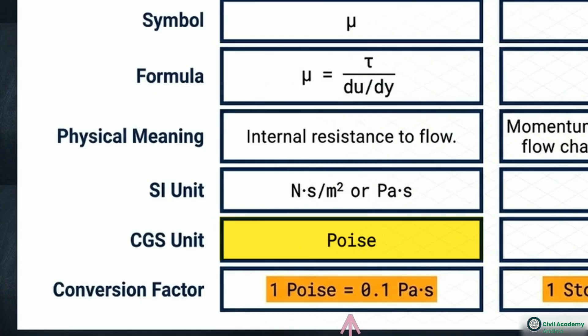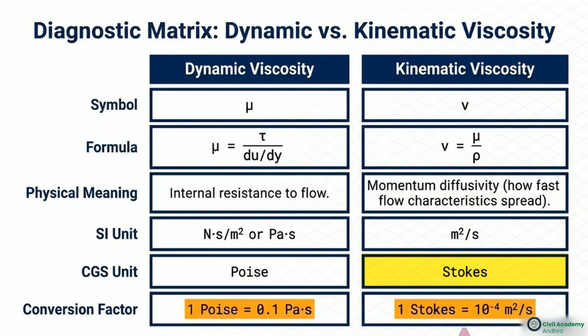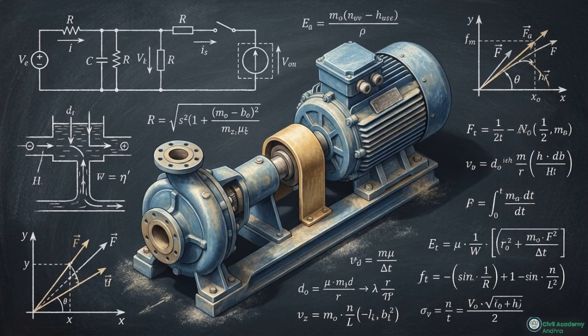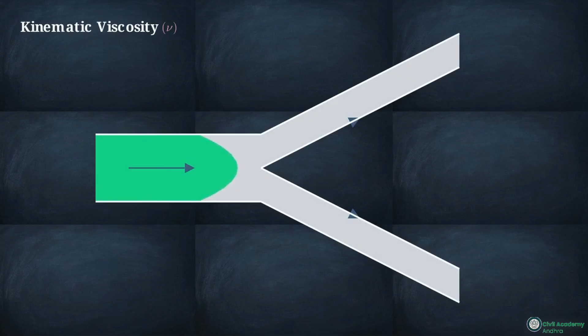If we take that dynamic viscosity and divide it by the fluid's density, we get kinematic viscosity, represented by nu. This removes the mass from the equation entirely, representing momentum diffusivity. The CGS unit for kinematic viscosity is the Stokes, which converts to a baseline of 10 to the -4 square meters per second. The distinction is vital. Dynamic viscosity tells an engineer exactly how much raw physical force is required to push a fluid through a pump. Kinematic viscosity dictates how fast the resulting flow characteristics will spread through the piping system.